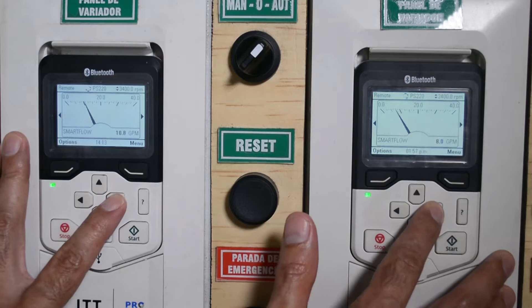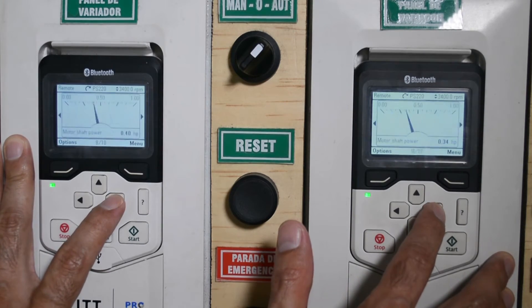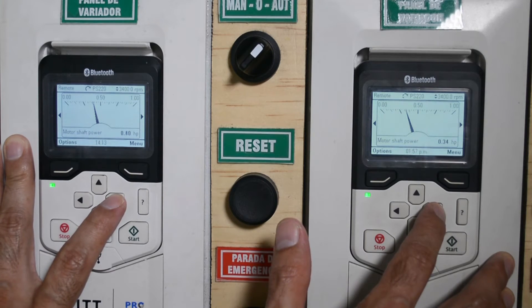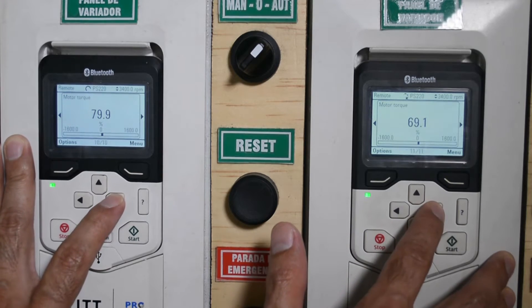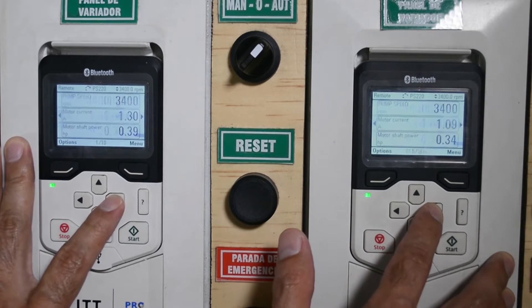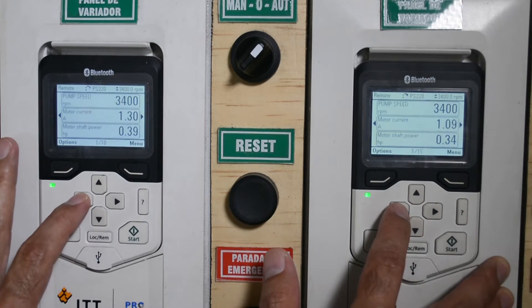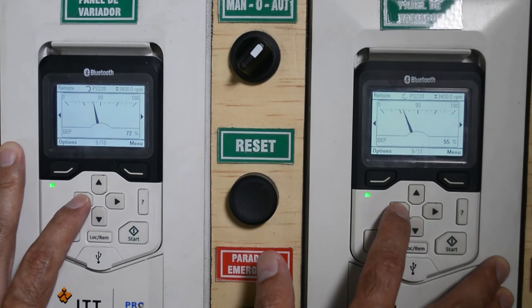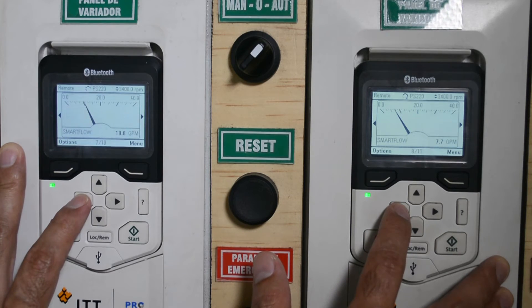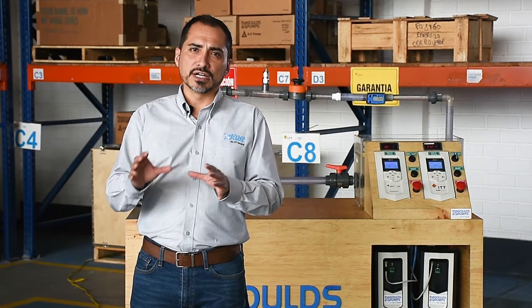Let's now run both pumps independently at about the same speed as before, 3400 RPM. We see that at the same speed, the performance is definitely not the same — one pump runs at 74% and the other at 54% of BEP. This is what we would see using standard variable frequency drives, and there is a big difference compared to the overall performance obtained by pump smart drives.